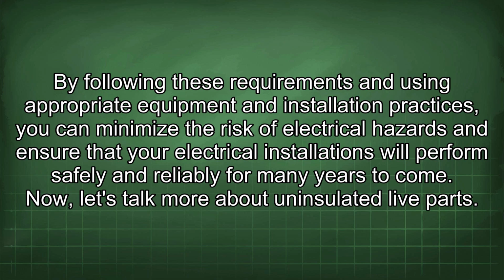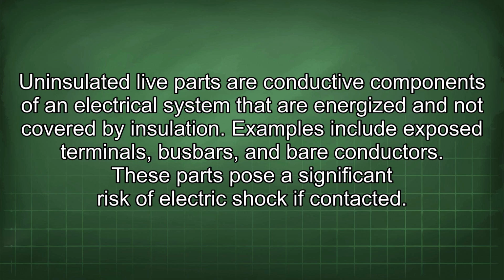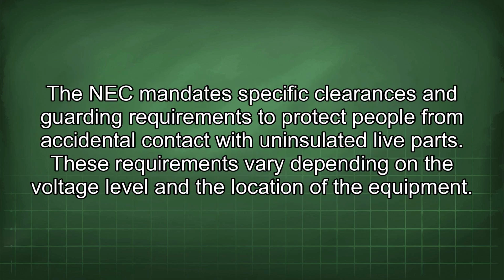Now, let's talk more about uninsulated live parts. Uninsulated live parts are conductive components of an electrical system that are energized and not covered by insulation. Examples include exposed terminals, busbars, and bare conductors. These parts pose a significant risk of electric shock if contacted. The NEC mandates specific clearances and guarding requirements to protect people from accidental contact with uninsulated live parts. These requirements vary depending on the voltage level and the location of the equipment.